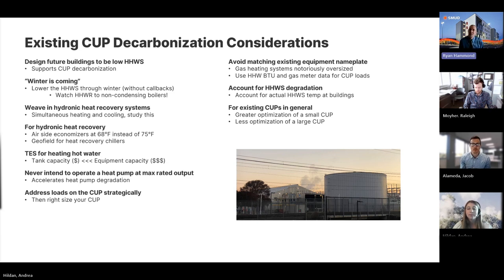Avoid matching existing equipment to nameplate. So you're looking to make the move forward. Don't get those engineers to match like for like. Tell them, no, you will not do this. You will study the heating hot water BTU meters we have and the gas meters we have. We'll get these loads right. Account for heating hot water supply degradation. Normally for a high temperature solution like 160 or 180 conventional solution, when the water gets out to your building, it's dropped a little bit in temperature, but it still works. Yes, it goes through insulated pipes, but all insulation does is it reduces heat loss. So there's still heat loss. When you're running lower heating hot water temperatures, just account for that.